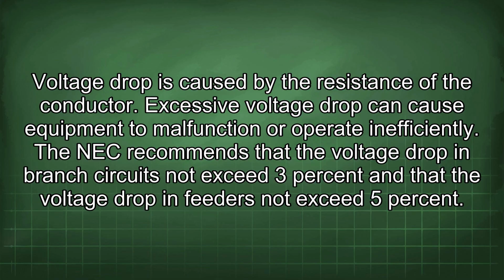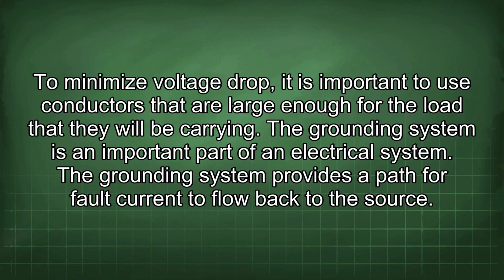The NEC recommends that the voltage drop in branch circuits not exceed 3% and that the voltage drop in feeders not exceed 5%. To minimize voltage drop, it is important to use conductors that are large enough for the load that they will be carrying.